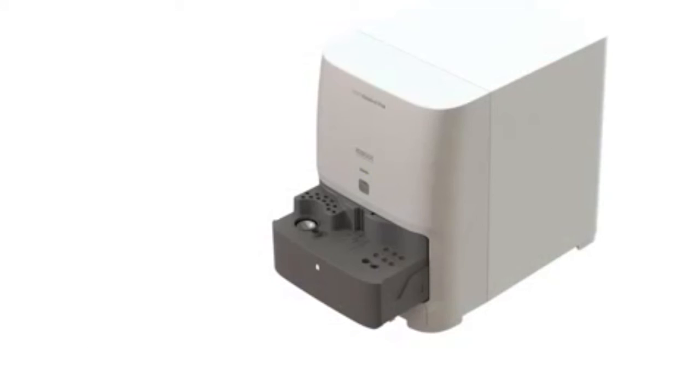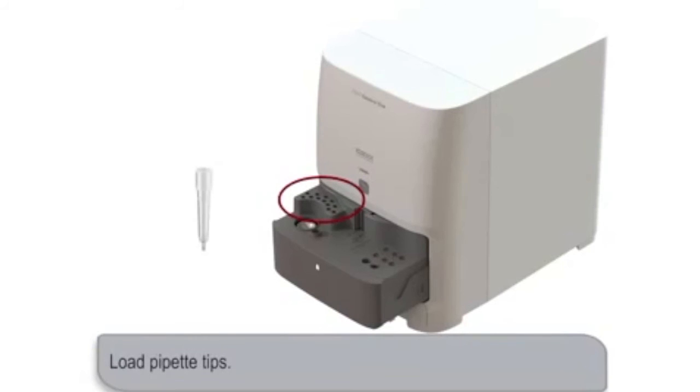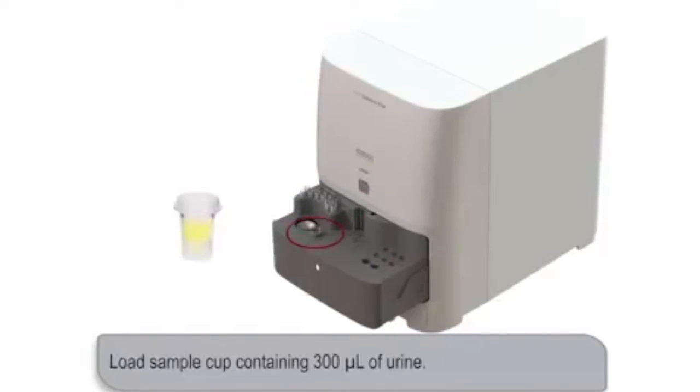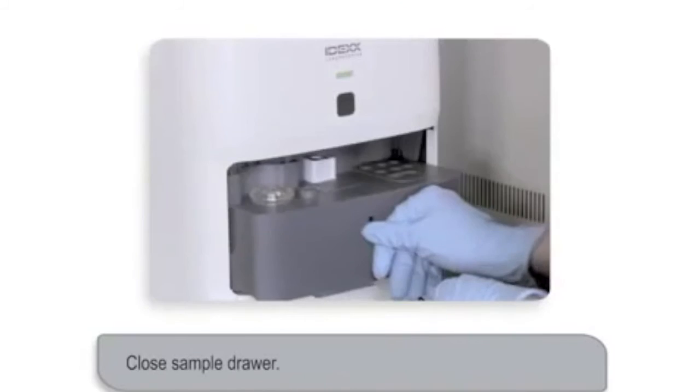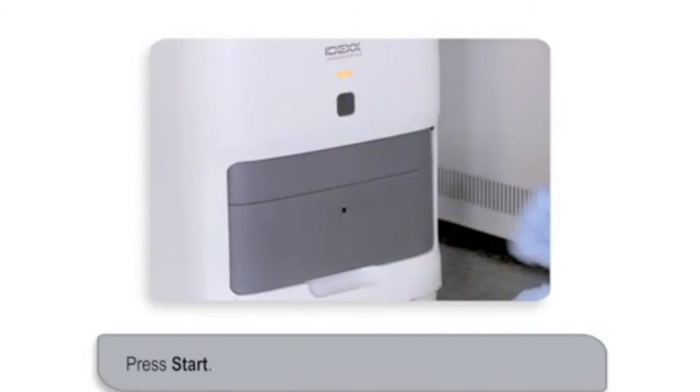Now it's time to load the materials into the Catalyst One Analyzer. First, ensure the pipette tip area of the drawer is full. Next, load the sample. Then, load the slides. Next, on the right side of the sample drawer, load an empty sample cup in the left front cup holder and a sample cup containing 300 microliters of Catalyst urine PC diluent in the right front cup holder. Close the sample drawer and then press the Start button.